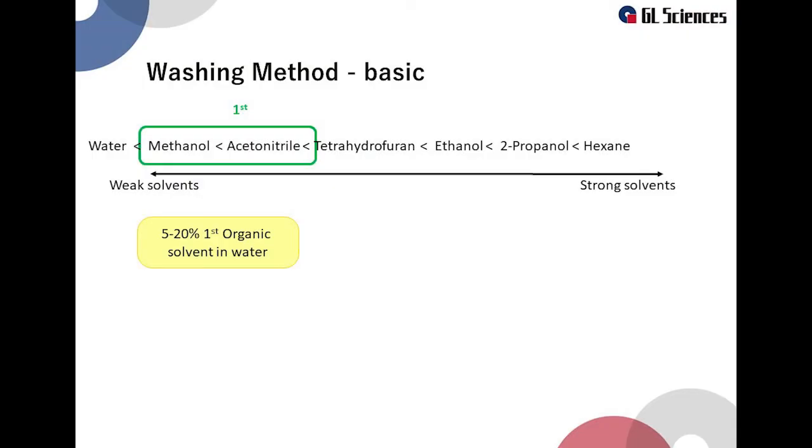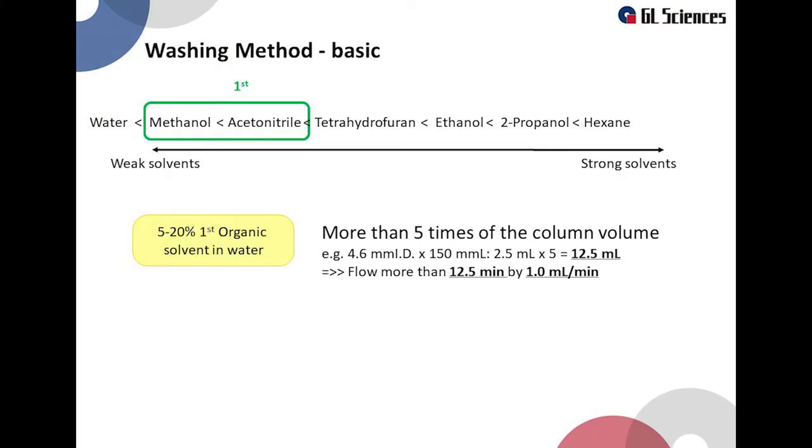First of all, create a mixture of 5-20% of the first choice detergents with water. Run this solvent through the column. The reason for flushing under water-rich conditions is to remove precipitated substances, such as salts, remaining on the column. The volume to use is more than 5 times the column volume. When washing at a flow rate of 1.0 ml per minute, running time must be at least 12.5 minutes.